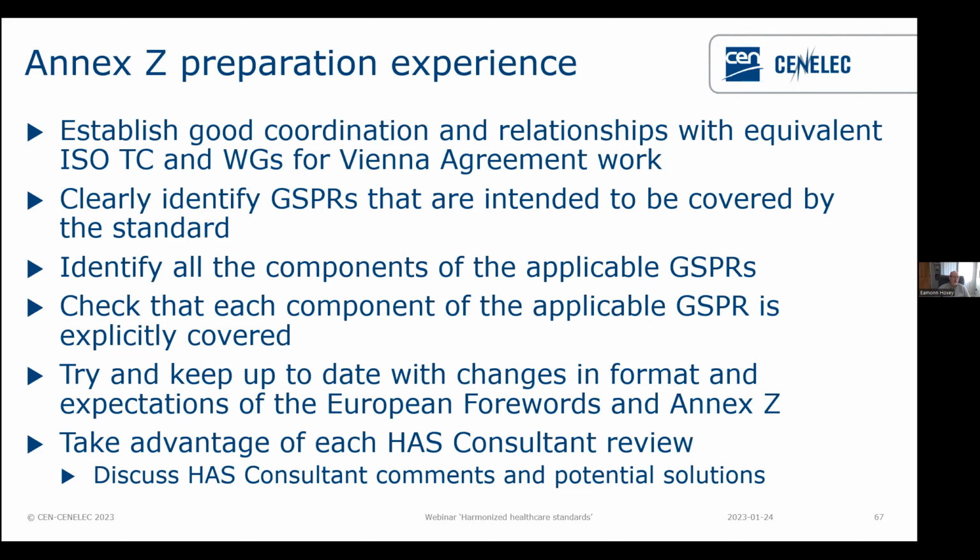It's very important to identify which GSPRs are intended to be covered and which aren't, and which components of the GSPRs are covered and which are not, because each of the GSPRs often has these compound requirements, and you need to make sure which aspects are covered and which are not.